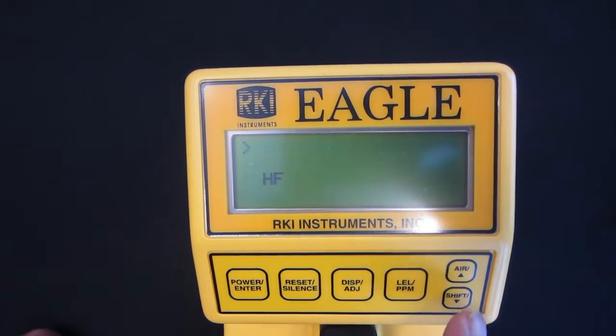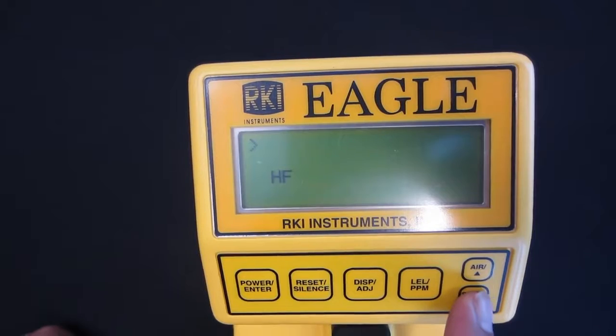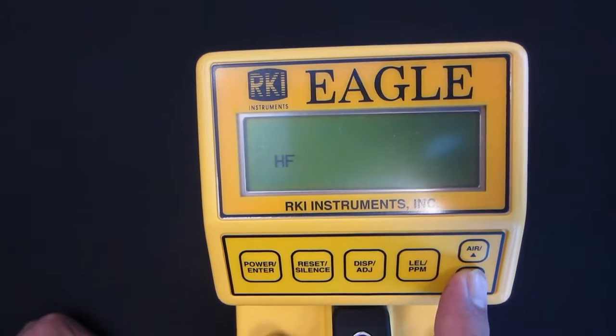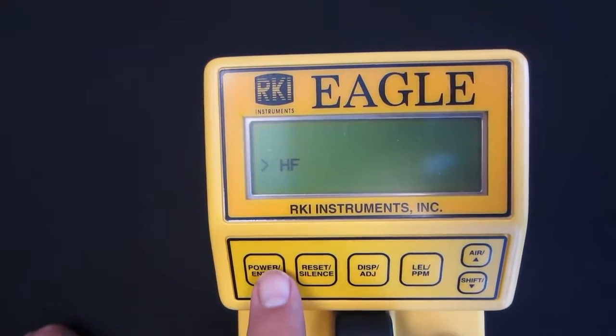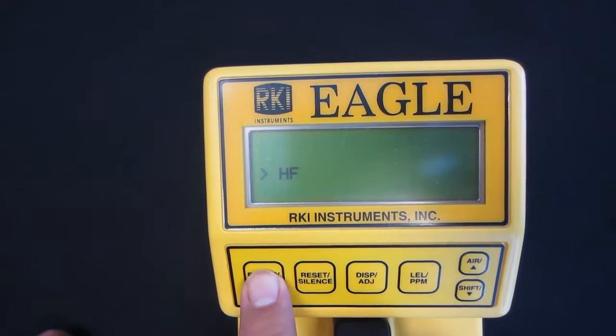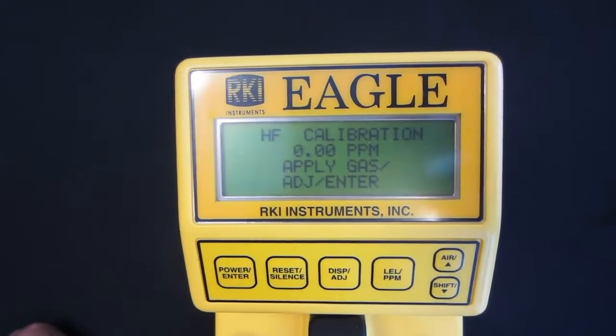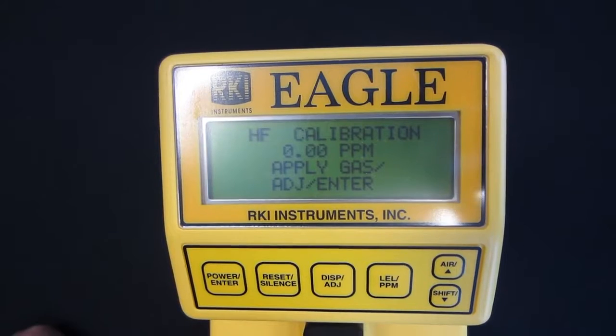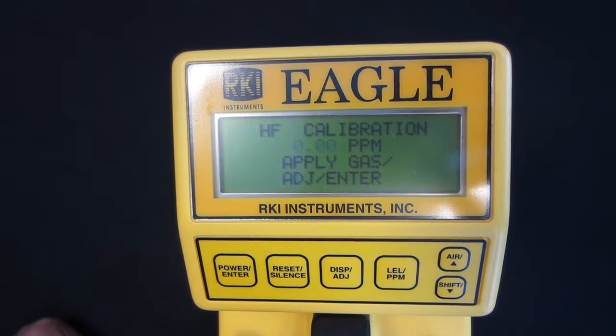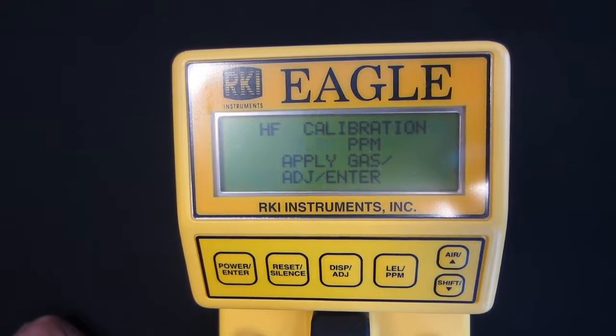And right now we want to bring that cursor down with our down arrow key to HF. And when it's at the HF position, we'll press power enter. And that brings us into the HF calibration. And right now we see 0 flashing. So right now the unit is ready to accept calibration gas. So we'll go ahead and do that.